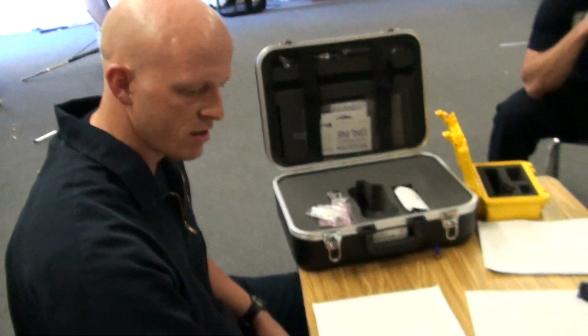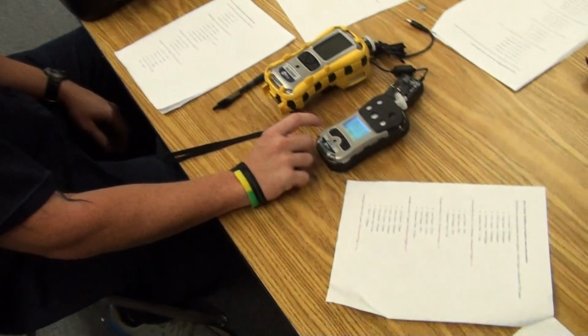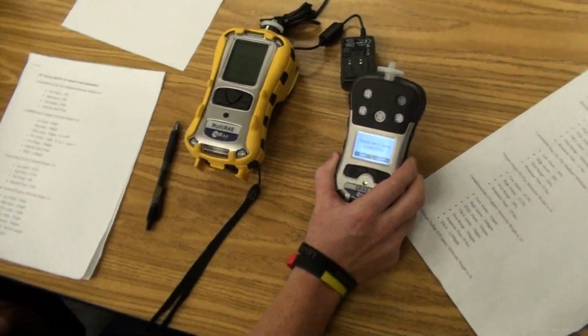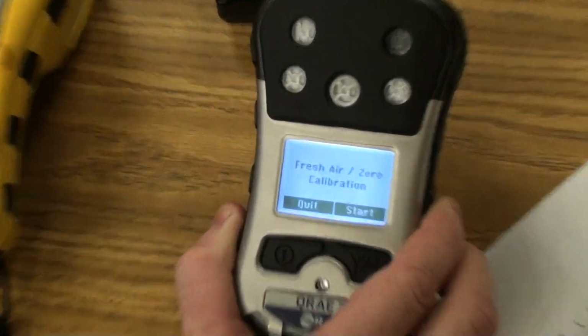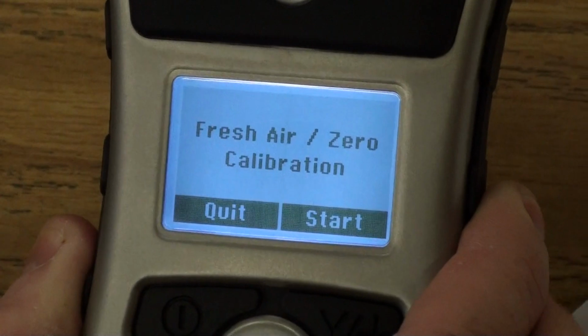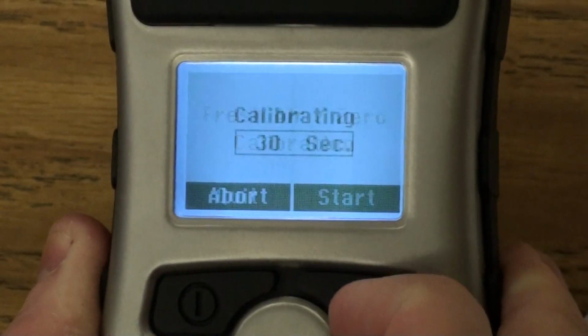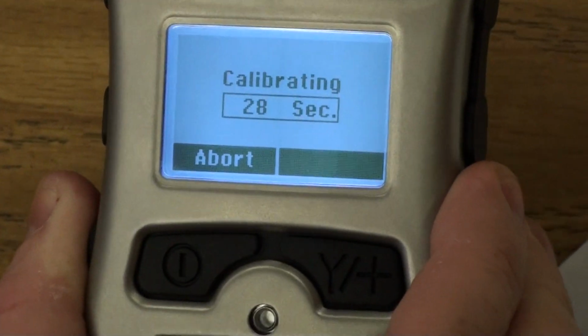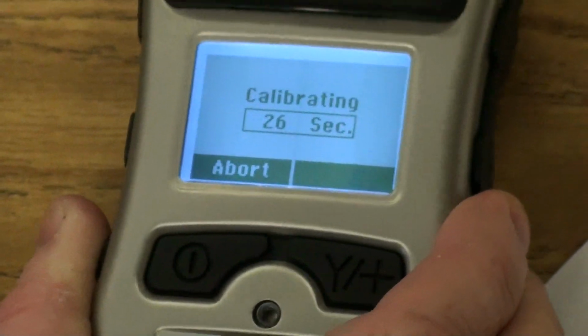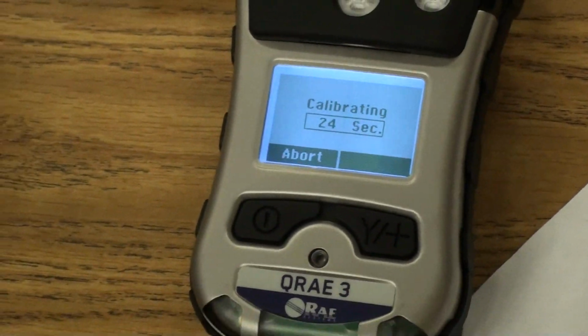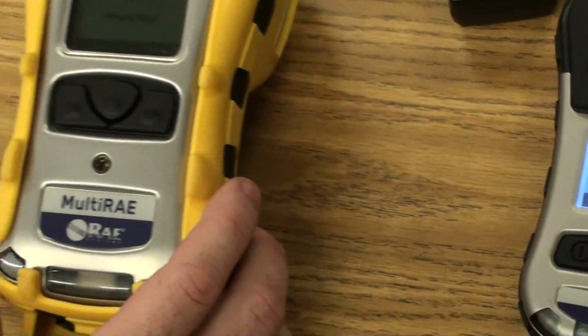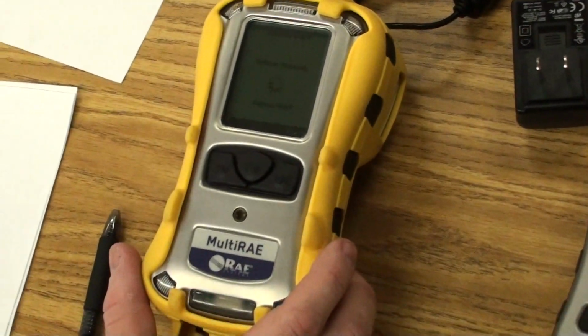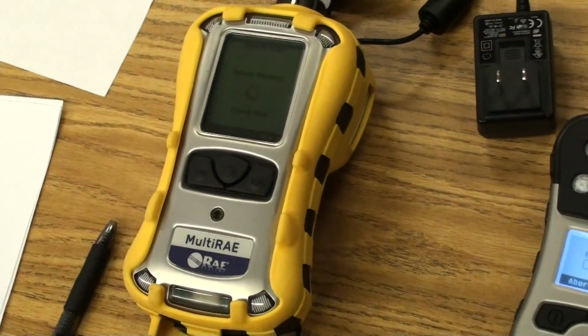Right now this one's done with its warm-up, and it's prompting to do a fresh air calibration. It says it right on the screen, just start or quit. Since we're just starting, we're going to hit start, and it's going to do a 30-second fresh air calibration. As soon as the MultiRAE is done, you do the same thing, but it takes an additional minute to do a fresh air calibration instead of 30 seconds.